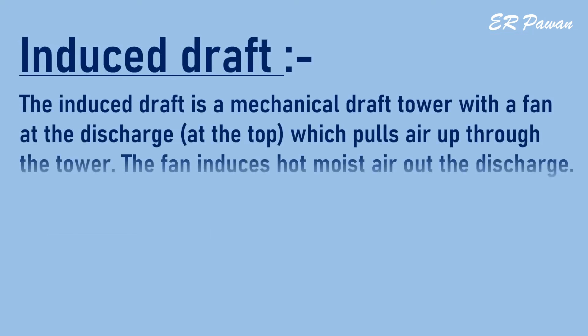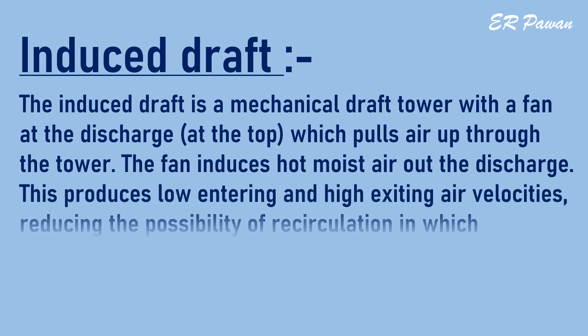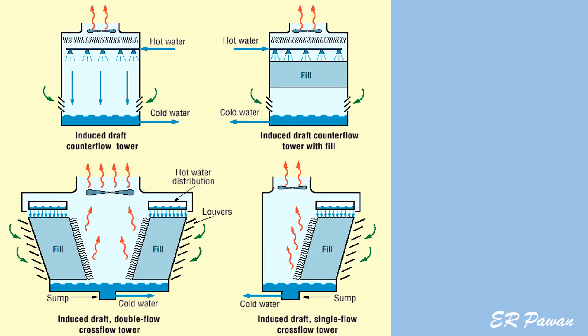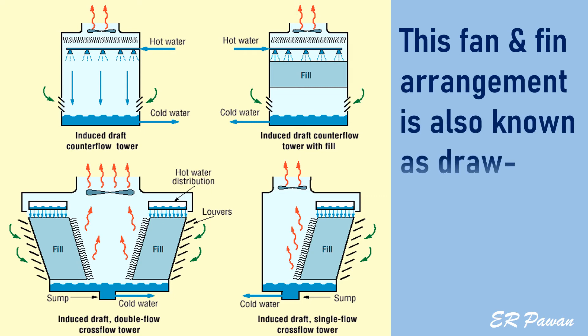Mechanical draft cooling towers consist of two types. Induced draft: the induced draft is a mechanical draft tower with a fan at the discharge at the top, which pulls air up through the tower. The fan induces hot moist air out the discharge. This produces low entering and high exiting air velocities, reducing the possibility of recirculation — in which discharged air flows back into the air intake. This fan and fin arrangement is also known as draw-through.